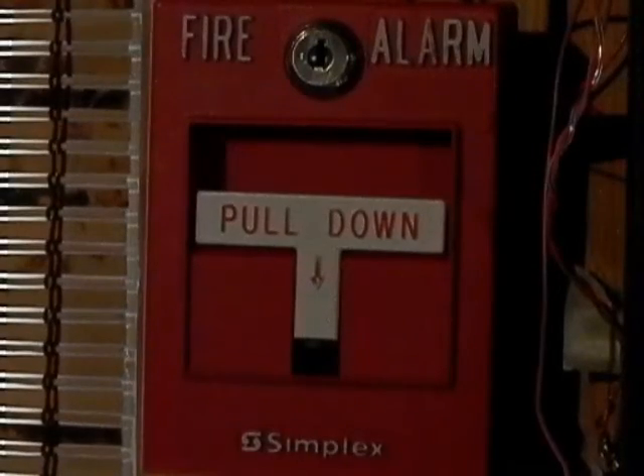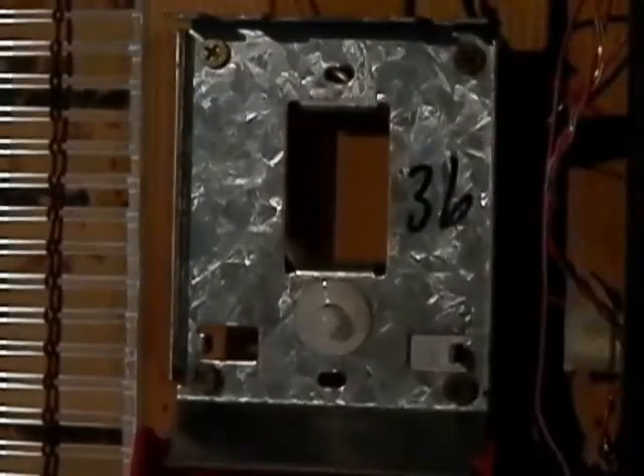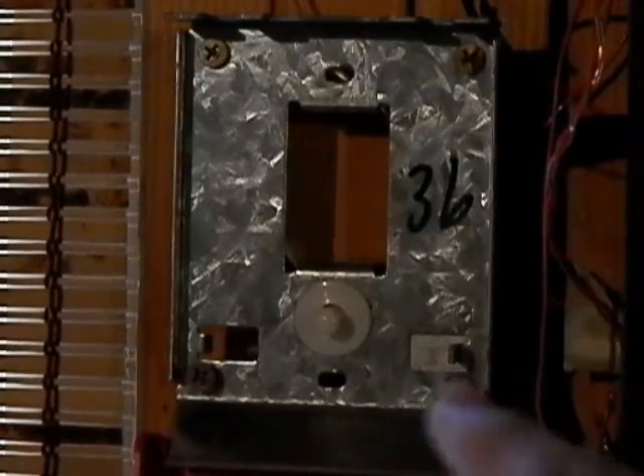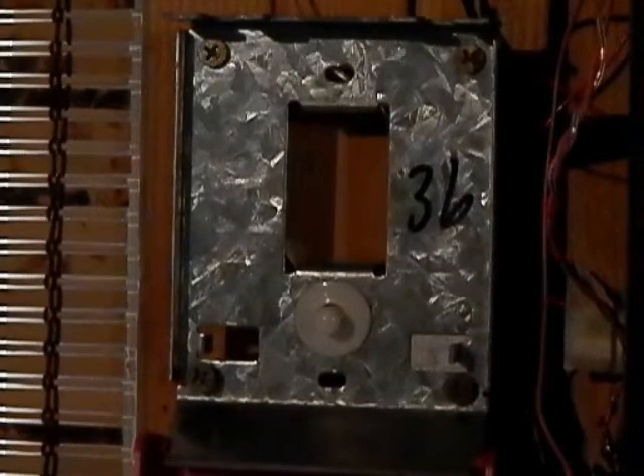There's a change to this pull station that I've made. Originally, this pull station used to just dangle on a hook — it wasn't stable, as you had seen in some of the videos. Now it is properly mounted. We've got four screws right there, there, there, and there. I'm using all my force to wiggle on it and it is not moving. That's a very nice improvement with that pull station.